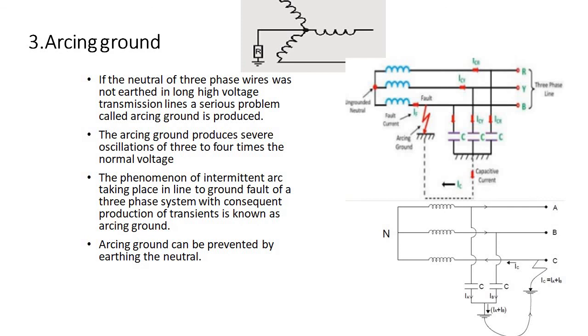Arcing ground. If the neutral of a three-phase wire system is not earthed in a long high voltage transmission line, a serious problem called arcing ground is produced. The arcing ground produces severe oscillation of 3 to 4 times normal voltage. The phenomenon of intermittent arc taking place in a line to ground fault of a three-phase system with the consequent production of transients is known as arcing ground. Arcing ground can be prevented by earthing the neutral.